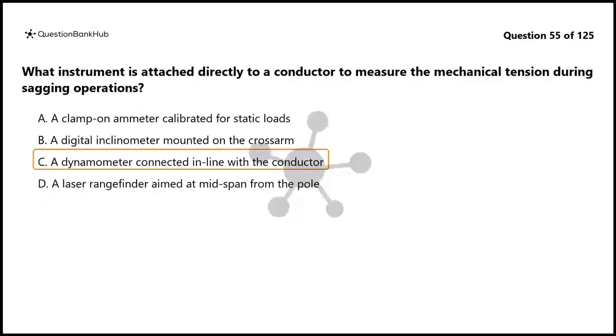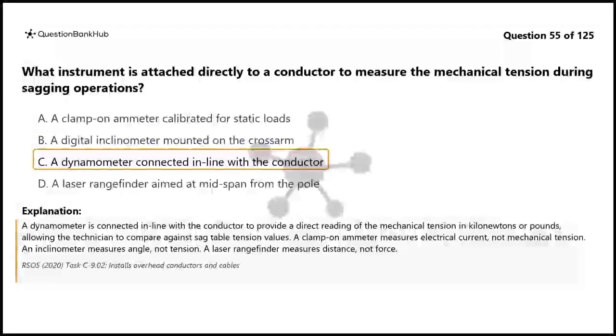The correct answer is C. A dynamometer is connected in line with the conductor to provide a direct reading of the mechanical tension in kilonewtons or pounds, allowing the technician to compare against sag table tension values. A clamp-on ammeter measures electrical current, not mechanical tension. An inclinometer measures angle, not tension. A laser rangefinder measures distance, not force.